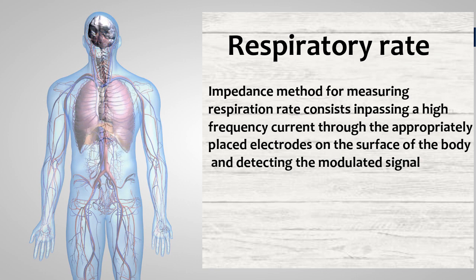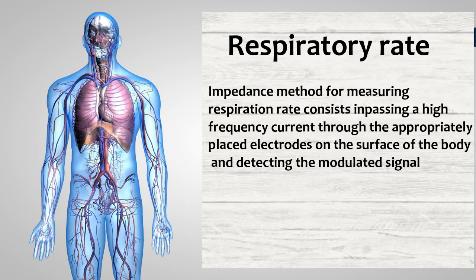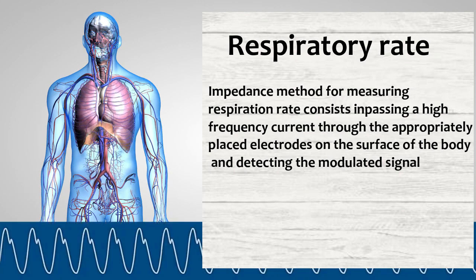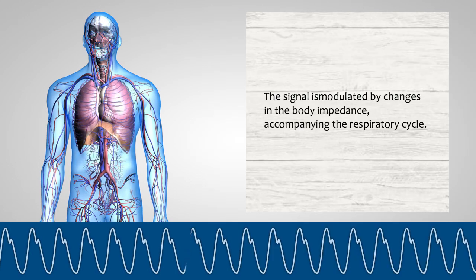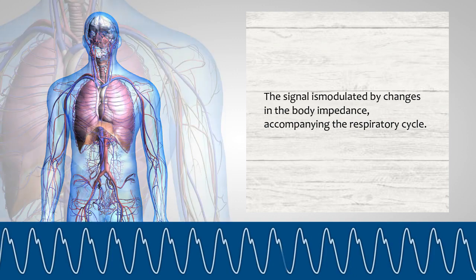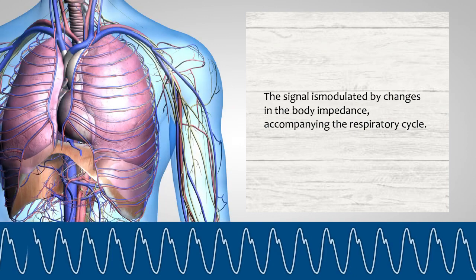The next measurement related to ECG leads is respiration rate. This is an indirect technique for the measurement of respiration rate. Using externally applied electrodes on the thorax, the impedance pneumograph measures rate through the relationship between respiratory depth and thoracic impedance change.